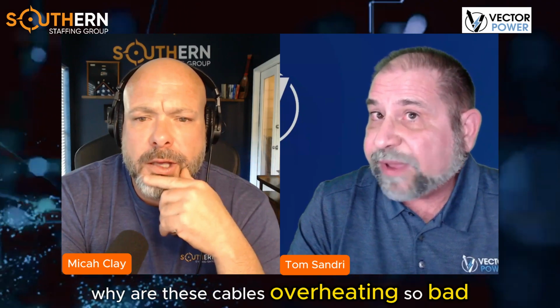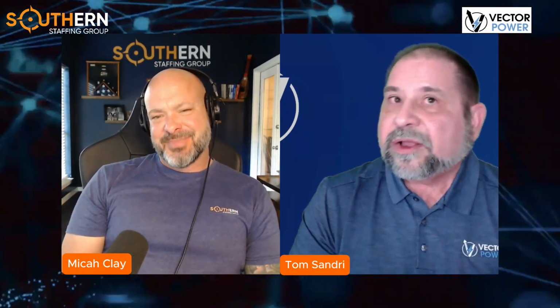So now it begs the question, why are these cables overheating so bad? We immediately go back to the owners of the wind farm and say, can you provide us some load data? What type of load currents have these cables been exposed to? No greater than about 550 amps, well within the design spec of the cable. That's not what we were expecting to hear.